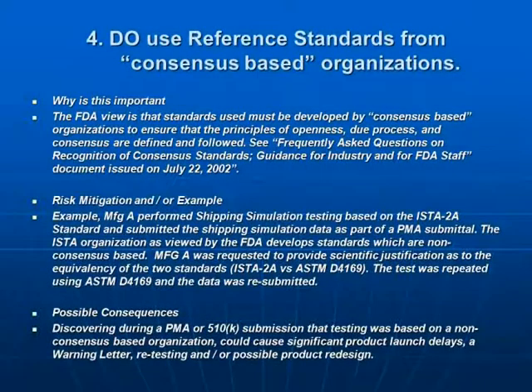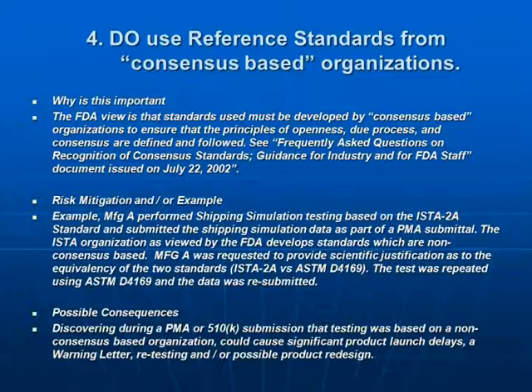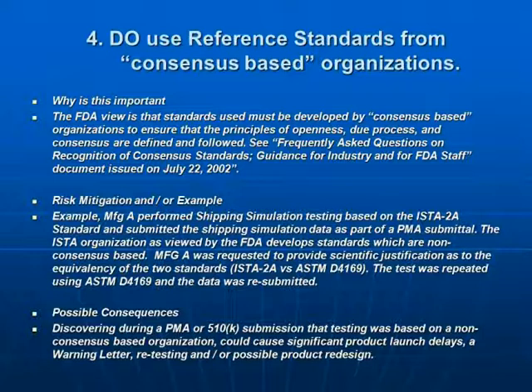The fourth do discusses reference standards and consensus-based standards organizations. Prior to performing any DVT testing, it would be wise to review any reference standards, ensure the most recent version is cited and used. Also, the FDA has a webpage titled 'Recognized Consensus Standards' that should be reviewed, especially if the product is a sterile product.